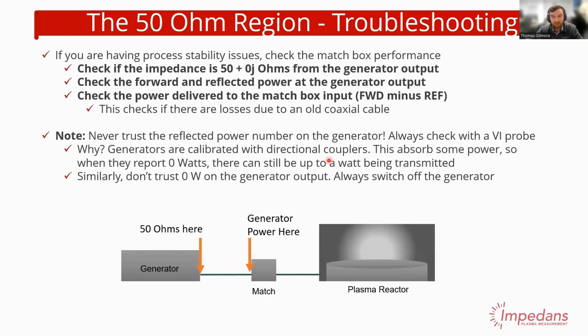Generators are typically calibrated with directional coupler technology. The way directional couplers work is they kind of take a bit of power off the line—they typically absorb some power. I've seen them absorb about 1 watt usually, which may not sound like a lot, but that means even when you're calibrating to 0, this thing is absorbing 1 watt. So the 0 on your reflected reading doesn't actually mean it's 0—it could be like 1 watt.